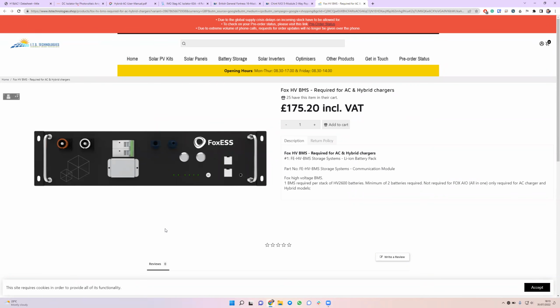It doesn't need to be off for very long. 2 minutes is probably excessive, but that will be fine. 1 to 2 minutes, not a problem. And then you're going to turn it all back on in the reverse order. So flick the circuit breaker across, switch the circuit breaker on, push this button. You'll notice the button stays recessed, and you'll see a little edge to the button once it's pushed in. That activates the batteries. These lights start flashing away.